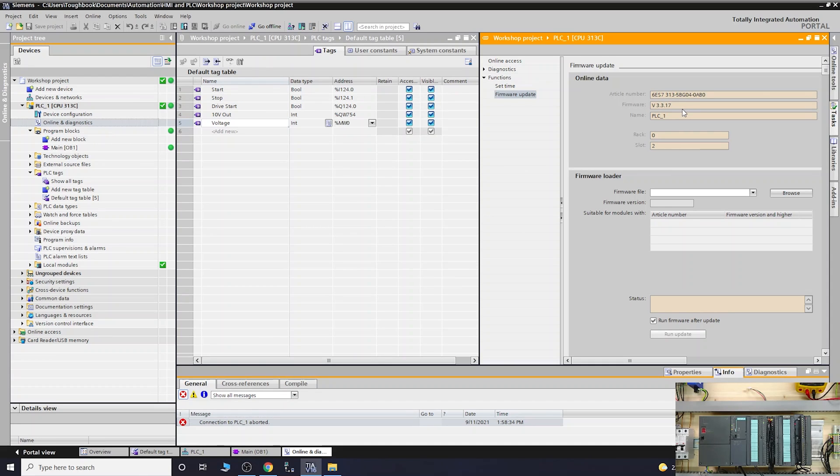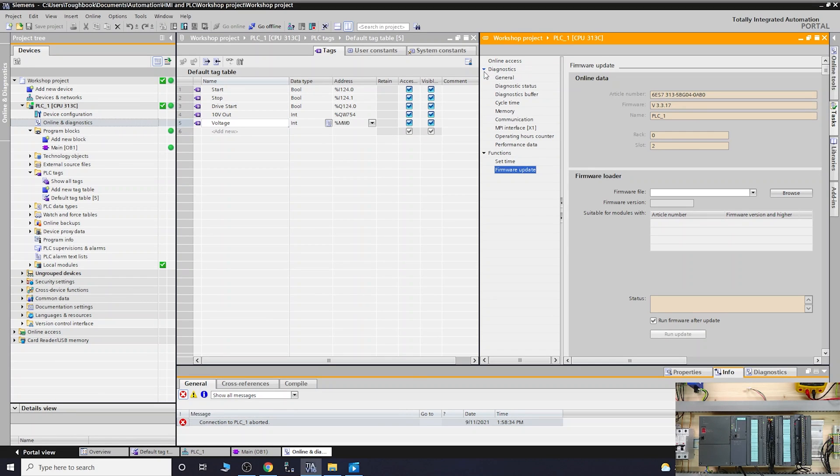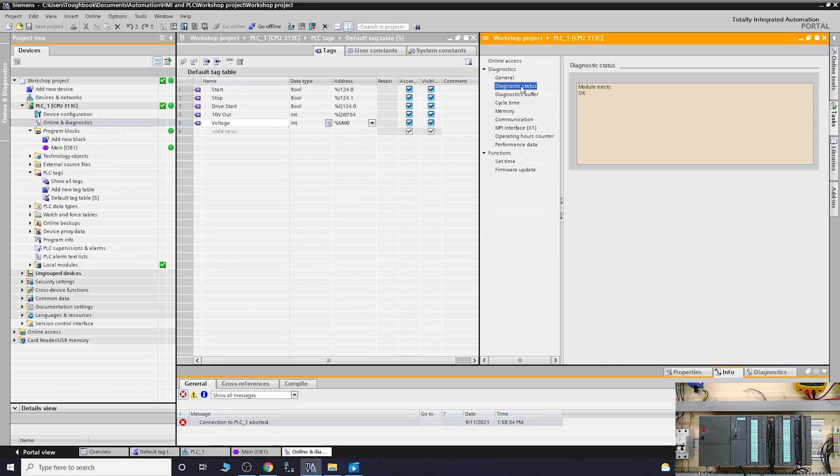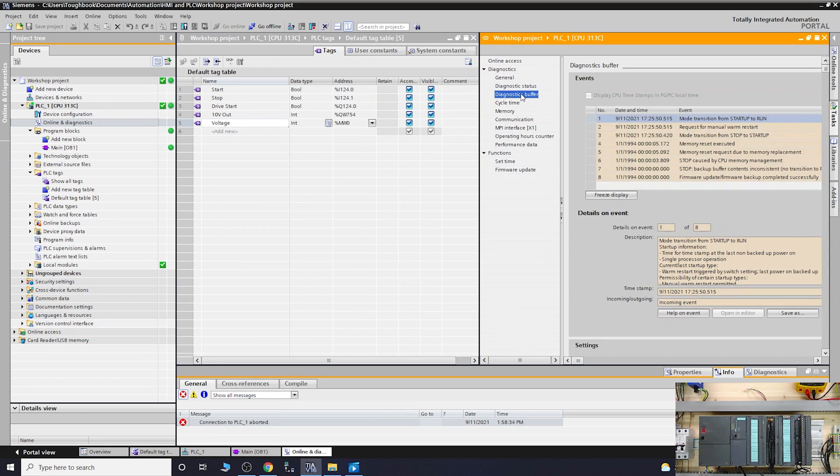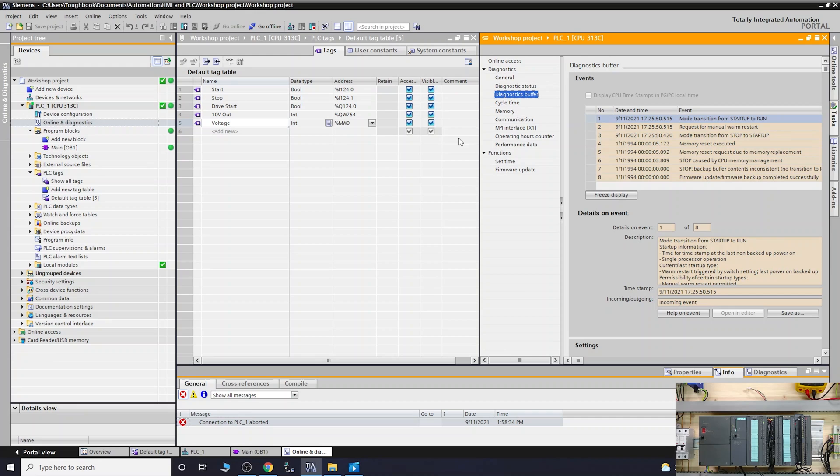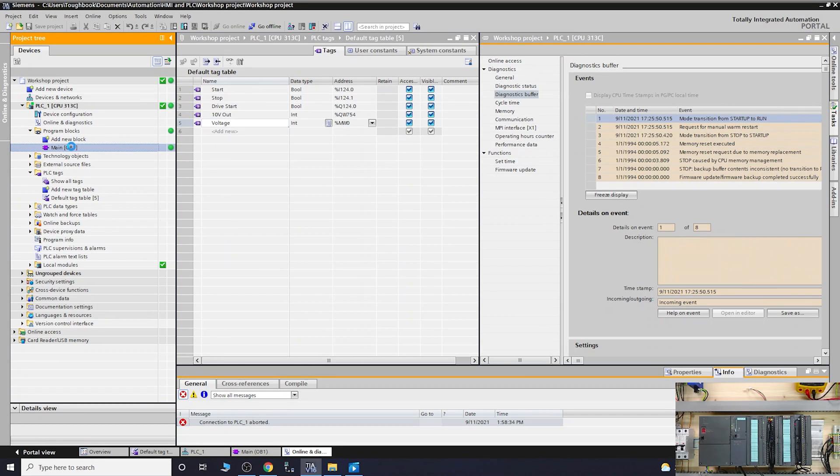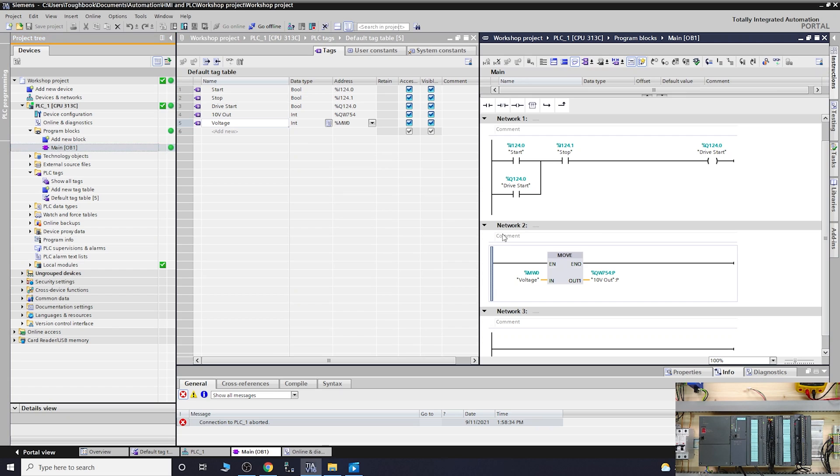Our firmware now is v3.3.17. As per Siemens' recommendations, let's go into diagnostics and look into the buffer. No problems have been reported, so everything is fine. Let's check if the program is still there, because technically it should not touch your program at all.